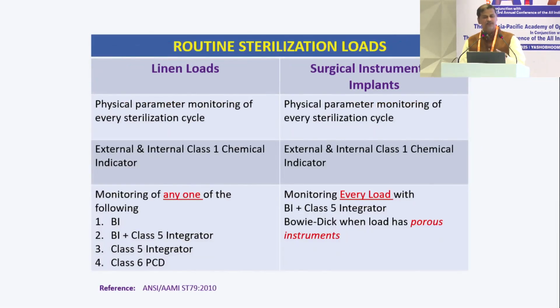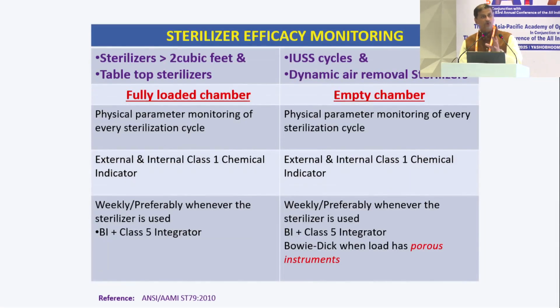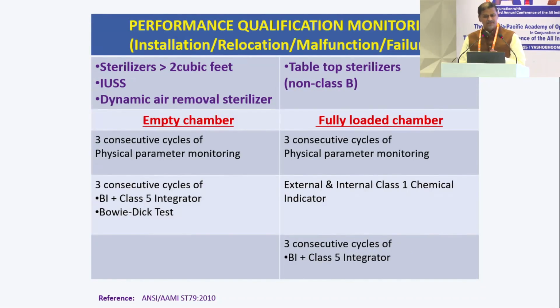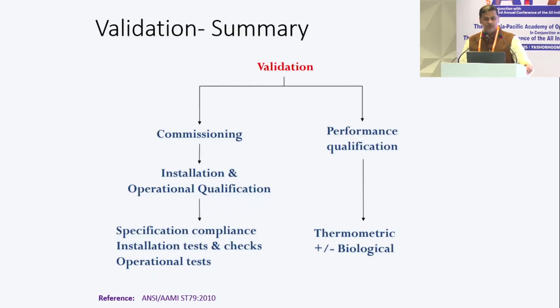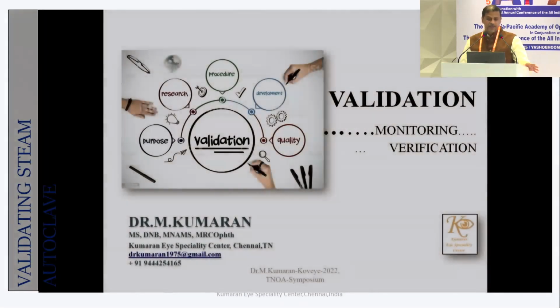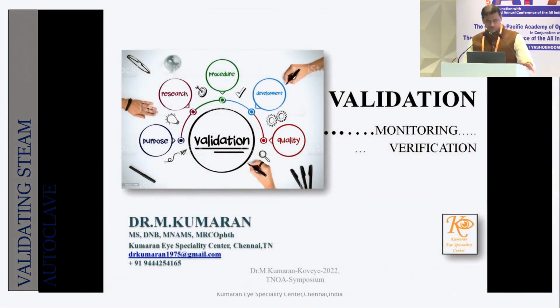So the first one is for your load. The second one is to monitor that the sterilizer is functioning well. This should be done in an empty chamber if it is a class S or a class N, and an IUS autoclave, and a loaded chamber if it is a gravity based autoclave. And this is, as I told you earlier, during an installation, relocation and malfunction, these are the parameters which have to be followed. So summarizing, there are commissioning and performance qualification indicators which have to be followed before you take up the indicators.